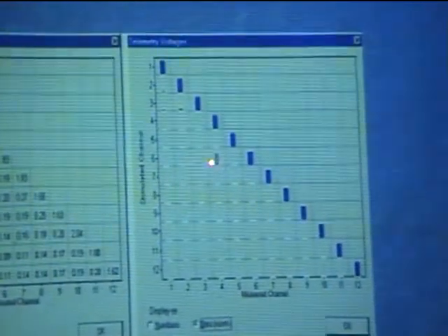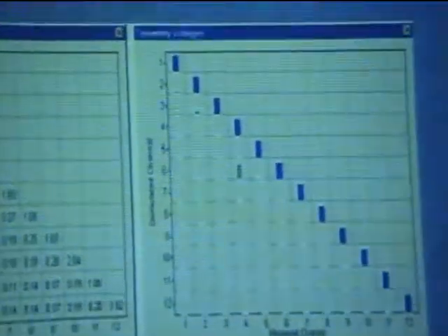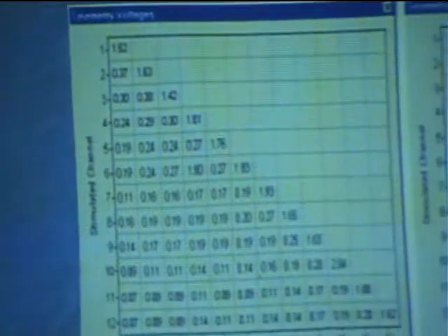Well, once you have this information, if you find that certain electrodes are short or if they are high, then there may be need to switch off those electrodes, because we cannot provide information through those electrodes and they need to be shut off.